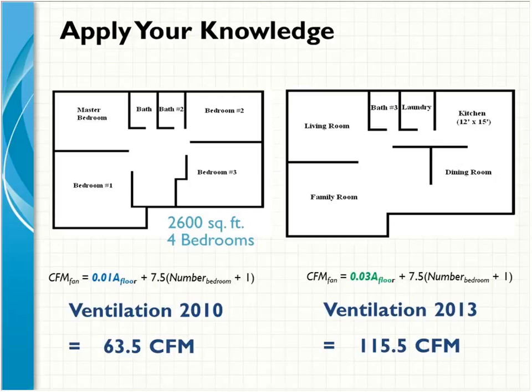As far as calculating, all of this information is available online, but just real quick, if you take a look at the left, you can see that the calculation there is that we want to have 7.5 CFM per bedroom plus 1, because we're going to assume there are 2 occupants in the master. So you count the bedrooms, add 1, and then multiply times 7.5, and then on the 2010 version, we're using a 1% floor space or conditioned space calculation. For this home here, the 2,600 square feet, 4-bedroom home, you're going to see that we would require 63.5 CFM. And in the 2013 version, using that 3% conditioned space calculation, that number would go up to 115.5 CFM.